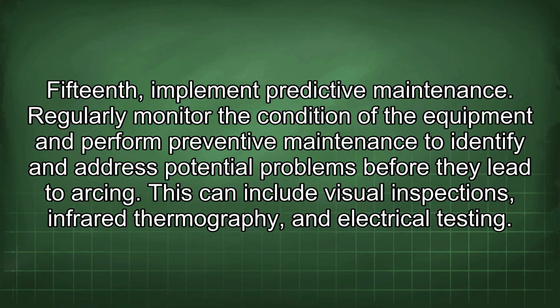15th, implement predictive maintenance. Regularly monitor the condition of the equipment and perform preventive maintenance to identify and address potential problems before they lead to arcing. This can include visual inspections, infrared thermography, and electrical testing.